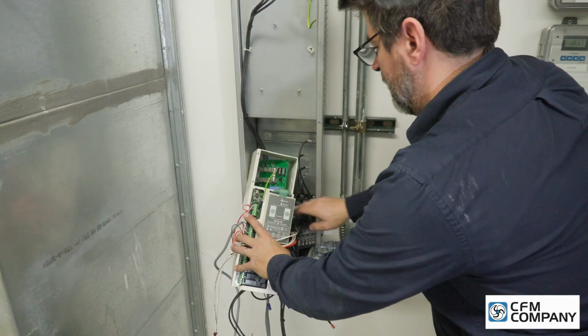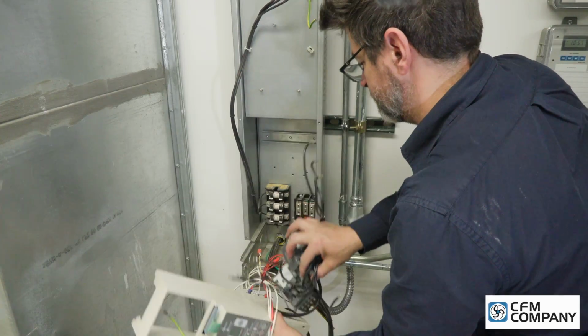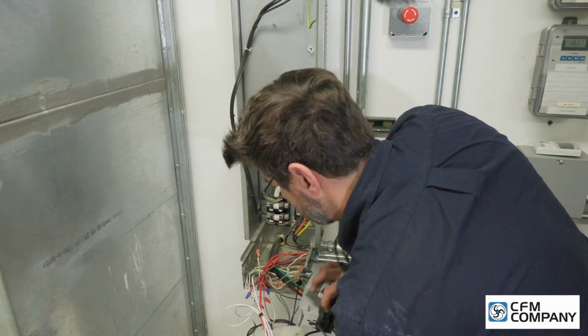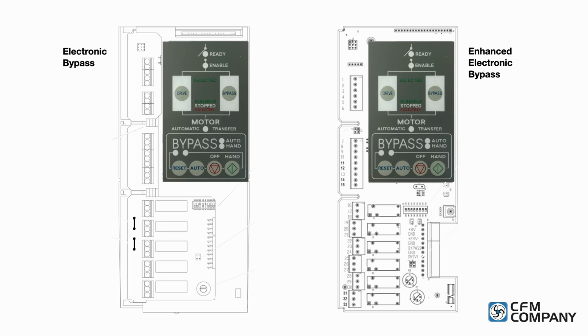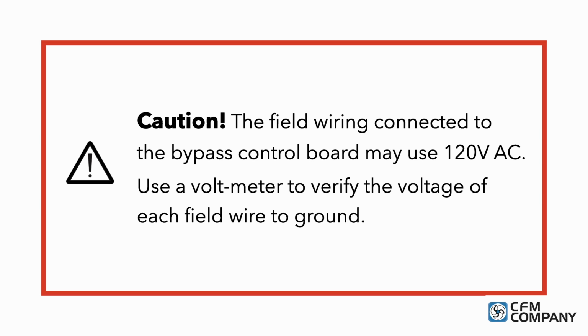During the bypass removal process, the electronic bypass control board was detached and moved to the side, while the original field control wires remained in place. Correctly identifying the function of the field wiring is dependent on the model of electronic bypass being worked on. The function of the terminals is different for each model. Caution: the field wiring connected to the bypass control board may use 120 volt AC. Use a voltmeter to verify the voltage of each field wire to ground.